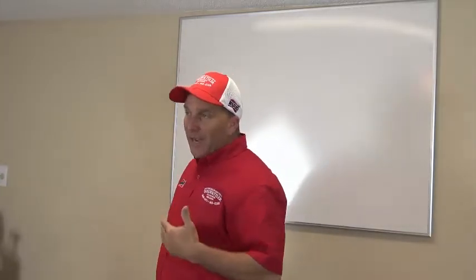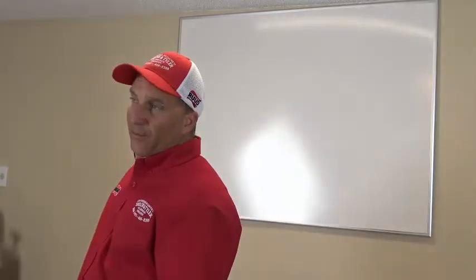But if you go to your thermostat and raise it up and bring it down, raise it up and bring it down, it will stop the short cycle. So you can sell a time delay on every system because it is an anti-short cycle device. Anti-short cycle is another word for time delay. If that power goes out, it's going to delay starting again for 5 minutes.